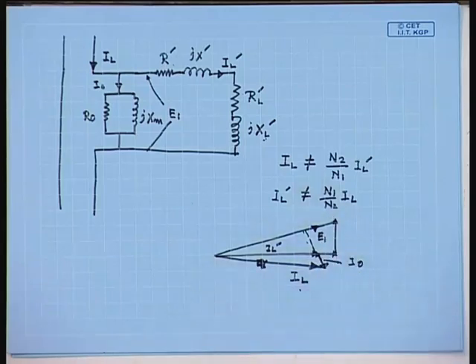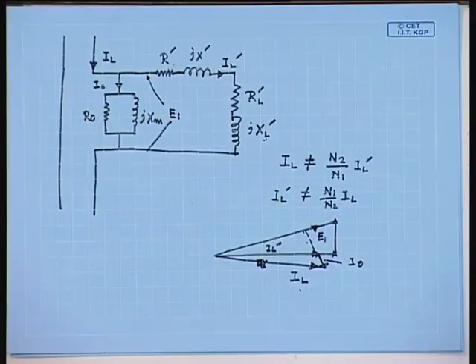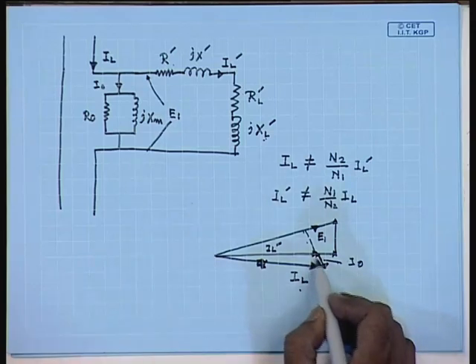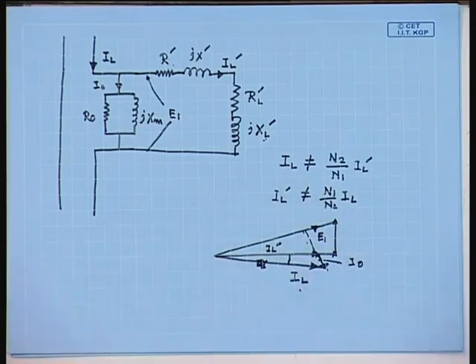In order for this calibration to hold, it is necessary also to make the impedance of the CT magnetization branch as high as possible. Otherwise, it will introduce both magnitude error and phase error. For current measurement, the magnitude error only is important, but when you want to measure power delivered to a load using potential and current transformers, in addition to the magnitude error, we should also take care of the phase error introduced by both these transformers. We will see this with the help of an example.